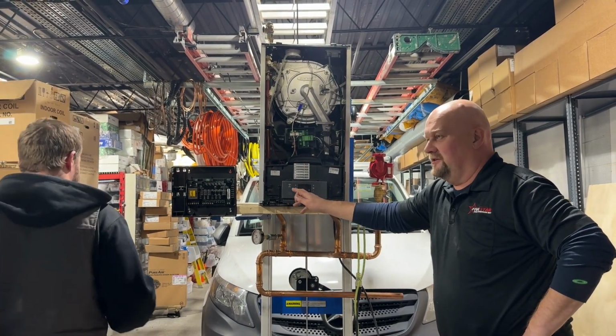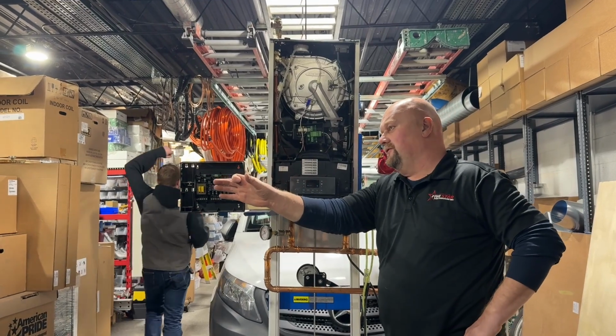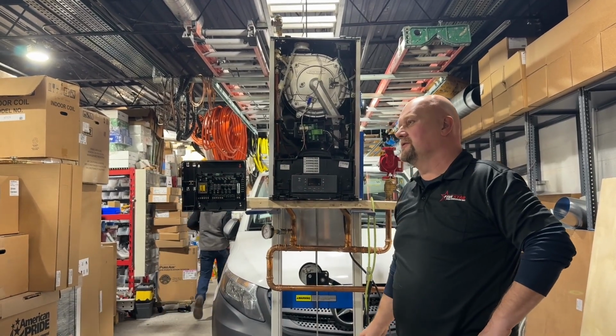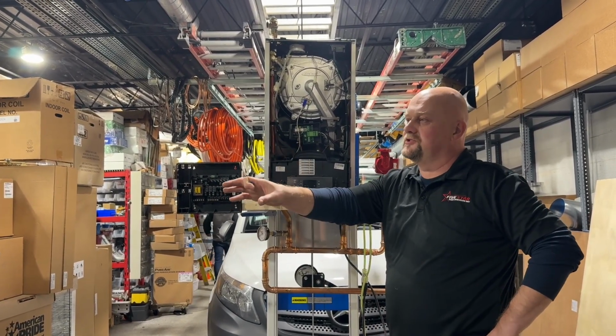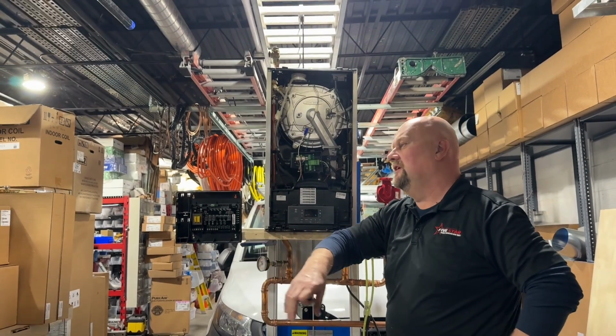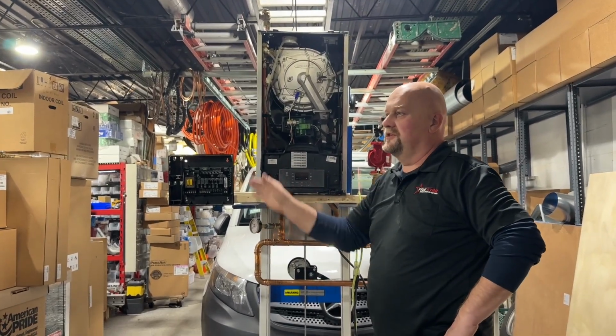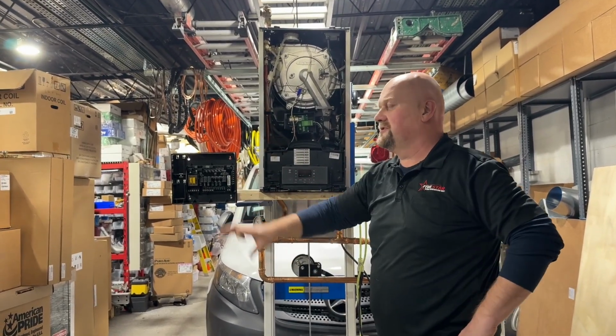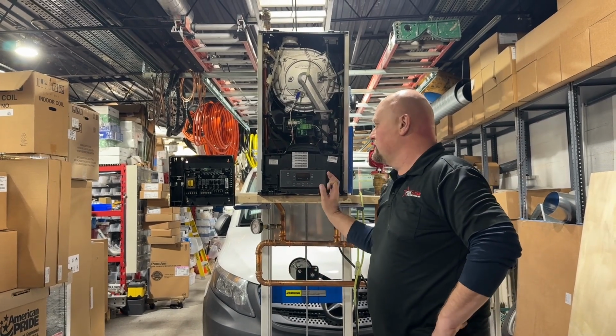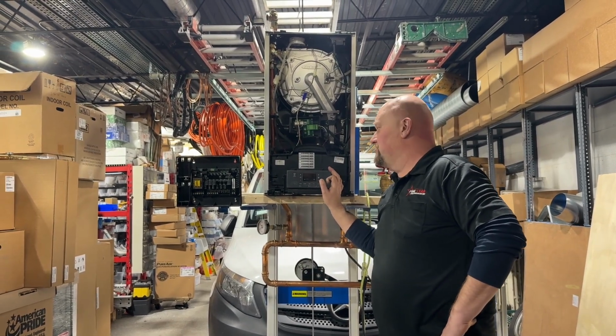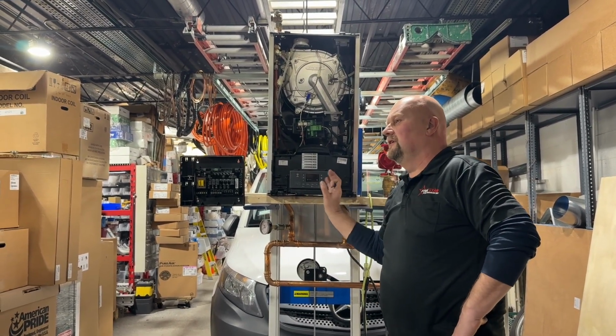If you're trying to heat up a storage tank itself, you want maximum 180 degrees, because that storage tank will have its own temperature reading and it'll shut the boiler off when it's 135 or 140 inside the storage tank. If this is a combi boiler, which this one isn't, it has a heat exchanger.